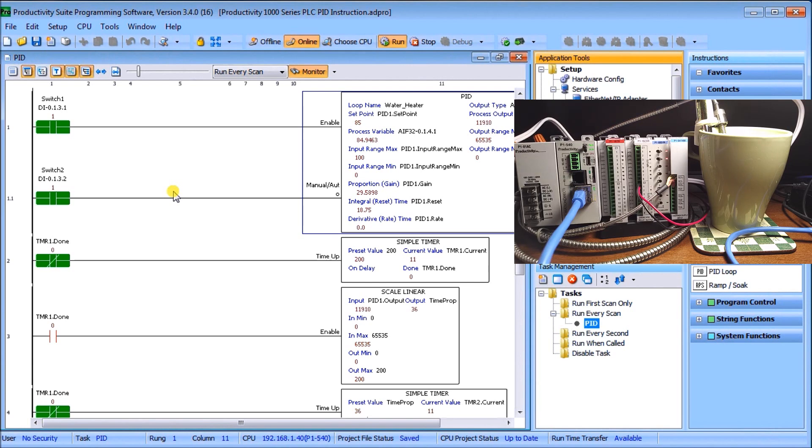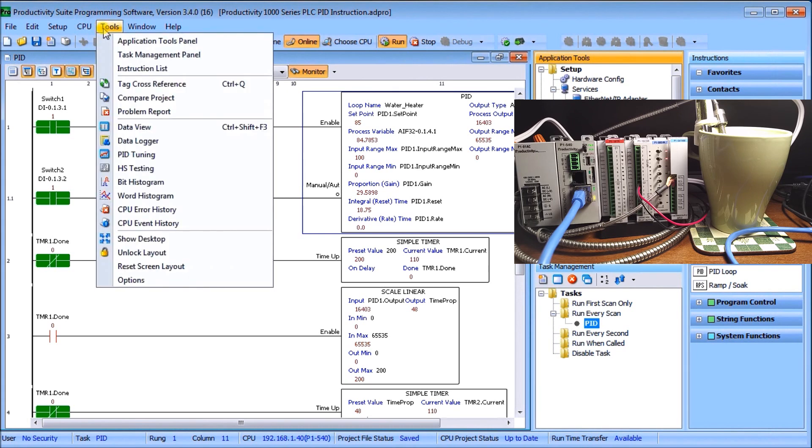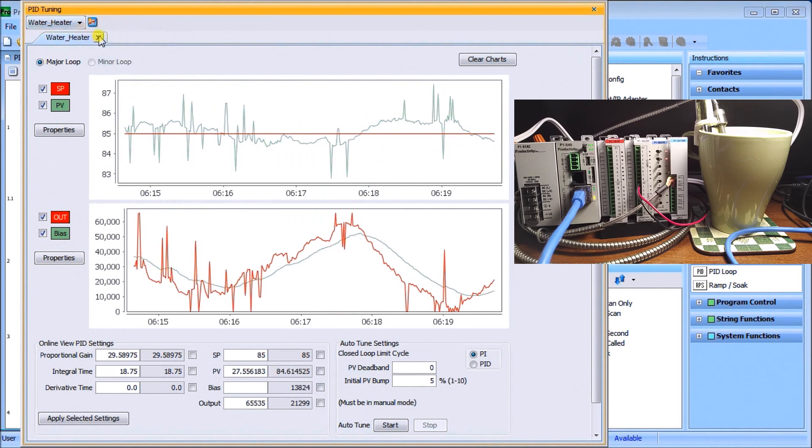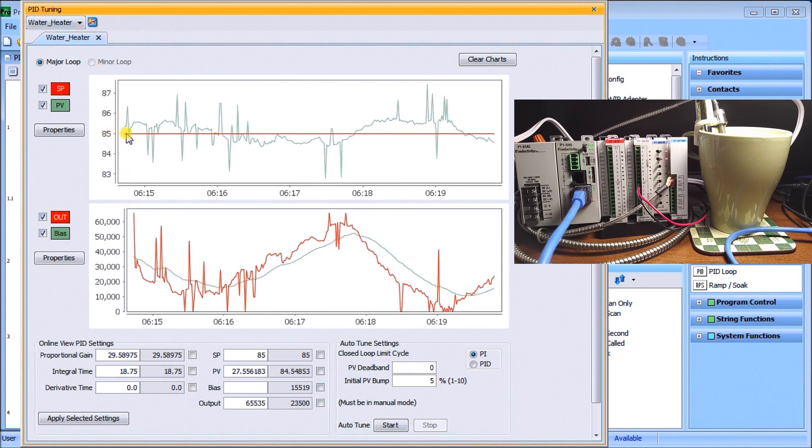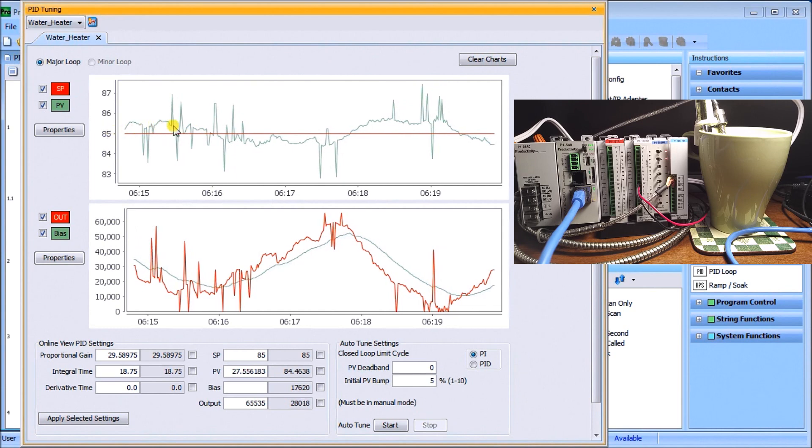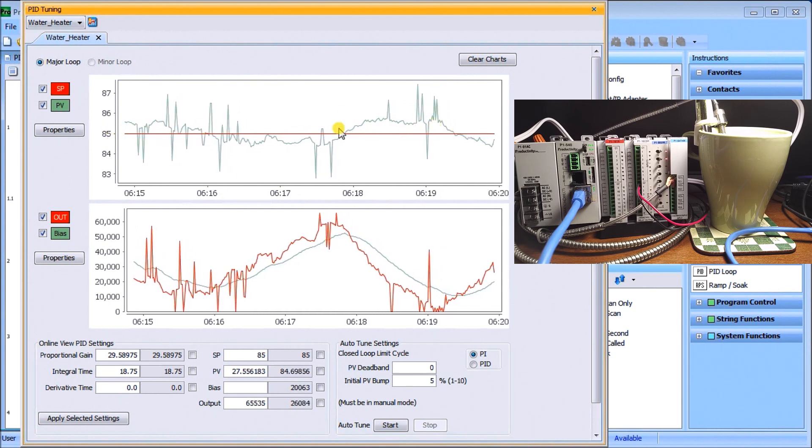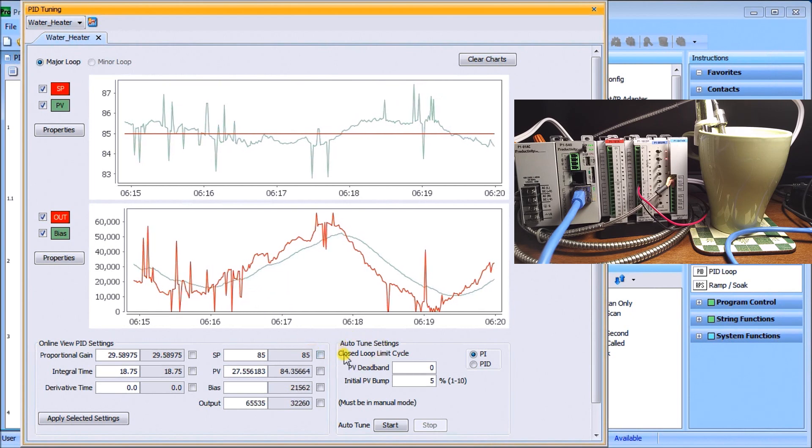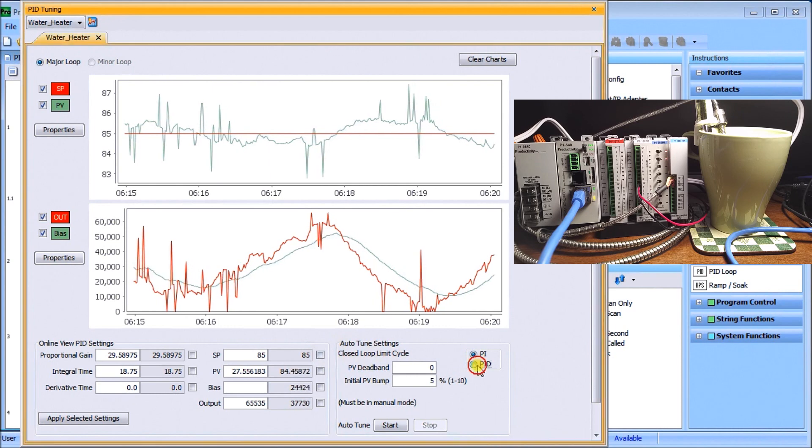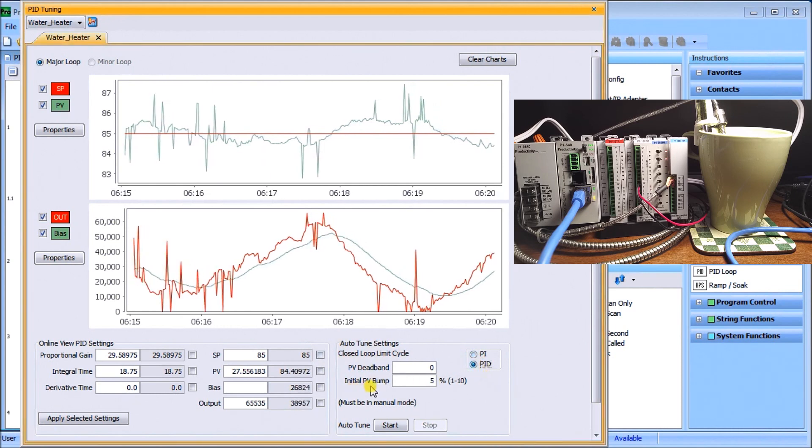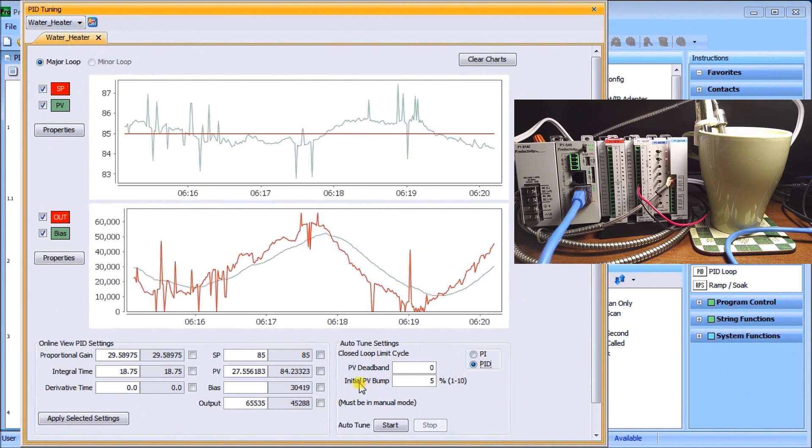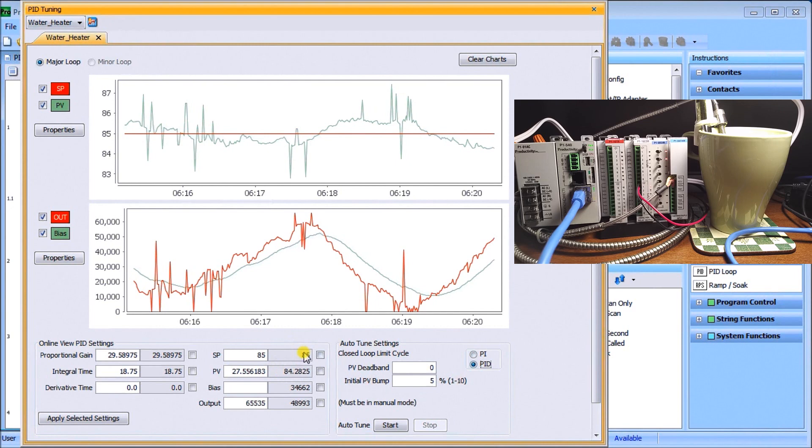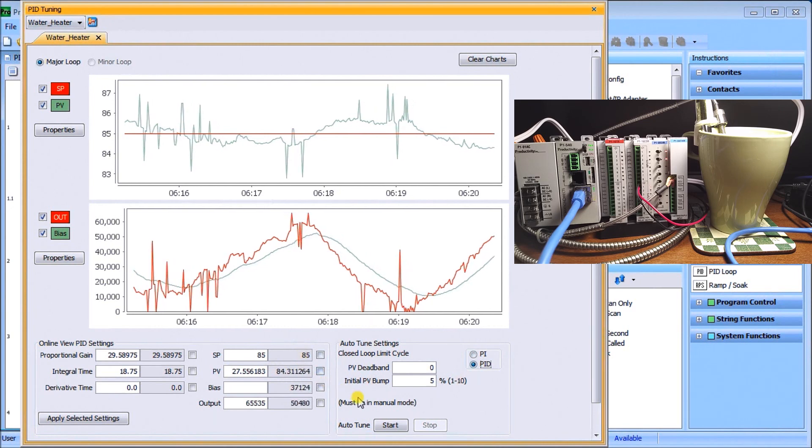If we call up under the tools, you will see PID tuning and we have our water heater, which is what we called it. You can see how there's our setpoint at 85 and this is how it's controlling right now. Then what we can do is take a look at my auto-tuning settings. You'll see that it's set right now for PI. Let's put it to PID, and then we can set the initial present value bump. What this will do is actually bump up that setpoint and it will take whatever the thermocouple reads at the time as the setpoint value, and it will then start doing calculations for my auto-tune.